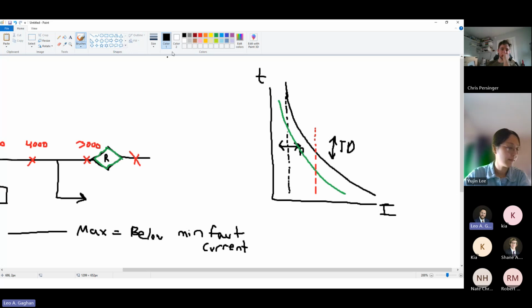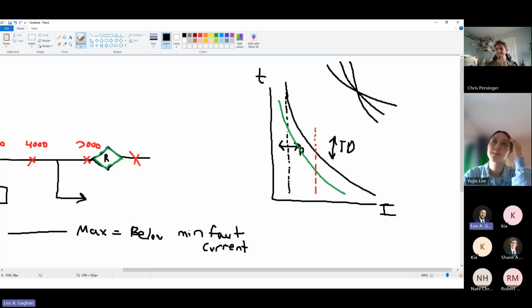And then lastly, that last setting that you can use for timing is called your curve selection. And I think we talked about it a while back. You've got options like inverse, very inverse, extremely inverse. And basically what that does is it can change you from more of a flat curve to a vertical curve to an extremely vertical curve. It kind of changes that characteristic so that you can make it fit your application the best you can.